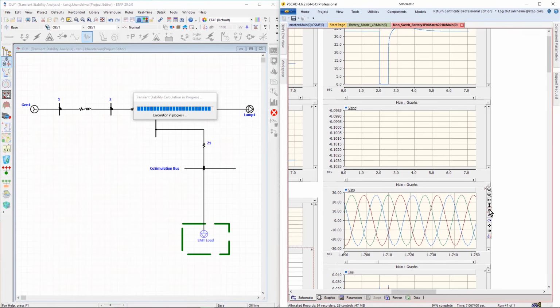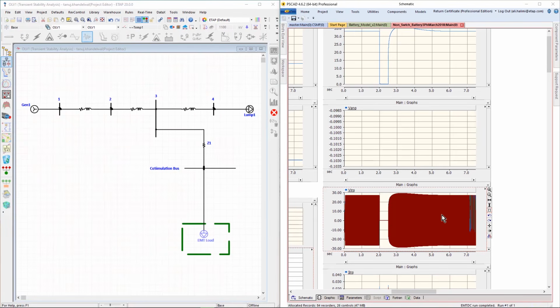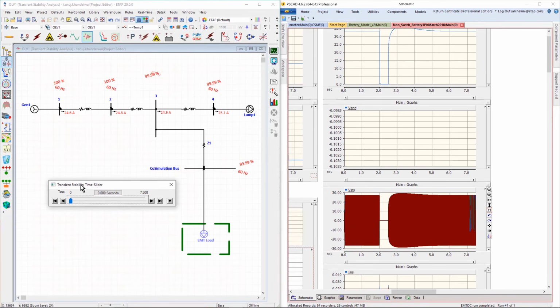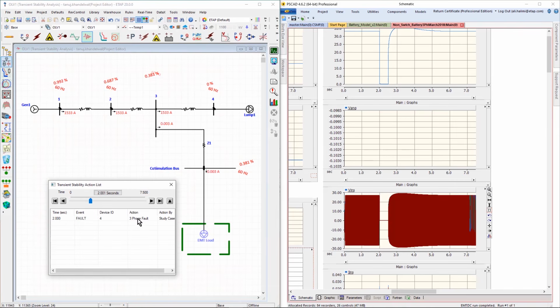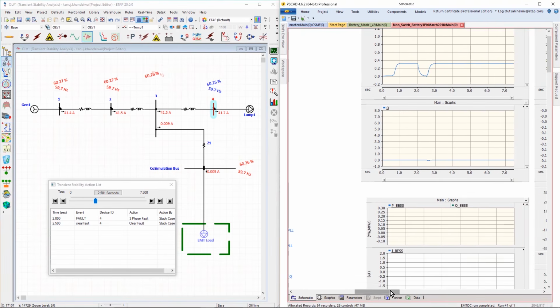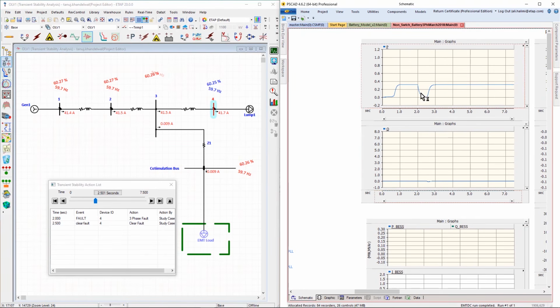You can of course utilize the capability to zoom the charts and observe that at this moment between 2 to 3 seconds there was essentially a disturbance that was created on the ETAP side, and that disturbance was essentially a fault at t equals 2 seconds that occurred at this particular bus in time, and the fault was cleared at 2.5 seconds. So we can observe that in EMT as instantaneous values, and you can also observe the interaction with ETAP on the RMS side.